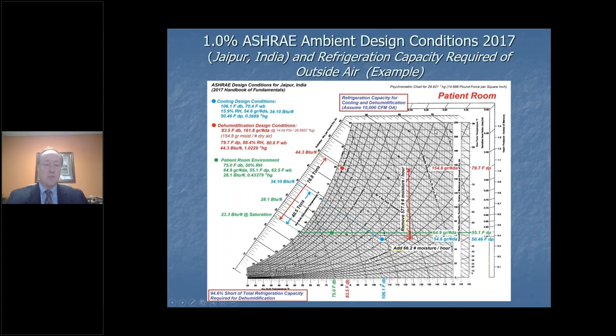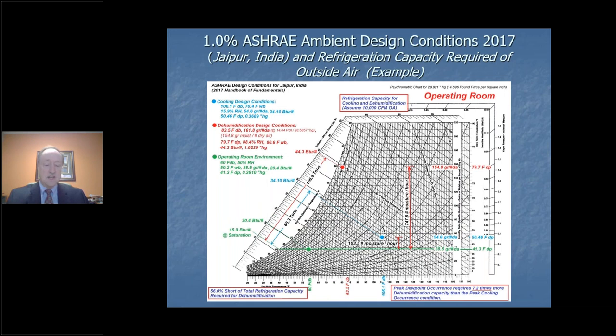What if we go to an operating room and the surgeon says, it is too warm in here at 65 degrees or 68 degrees, I want 60 degrees in here. So you drop down to 60 degrees and you run through the same calculations that I just did. Just for 10,000 CFM of outside air, the ventilation air, to go from this point to this point required 106 tons of cooling or refrigeration capacity.